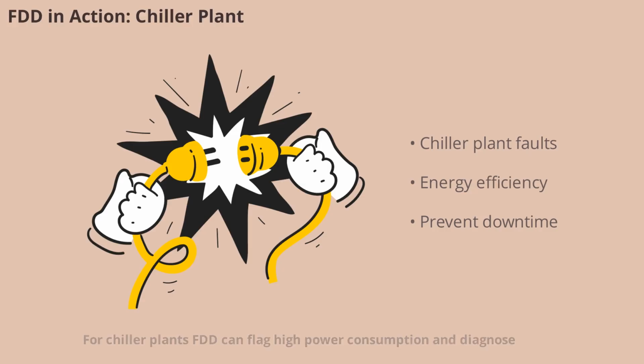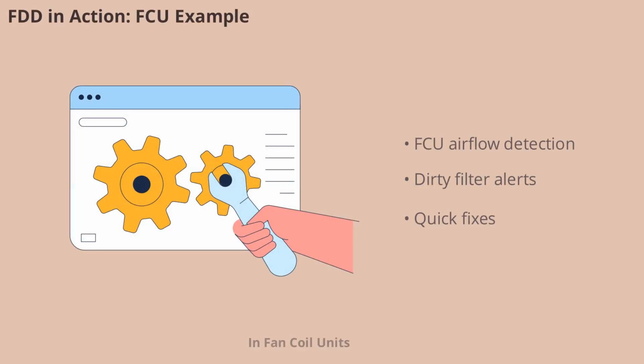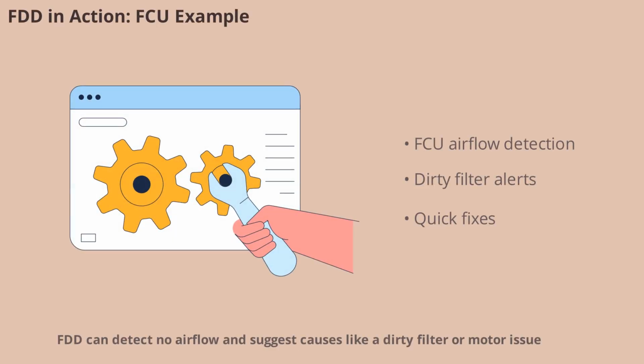For chiller plants, FDD can flag high power consumption and diagnose issues like a failed condenser or poor sequencing. By identifying these problems early, the system helps maintain energy efficiency and prevents costly downtime. In fan coil units, FDD can detect no airflow and suggest causes like a dirty filter or motor issue. This rapid identification allows for quick fixes, ensuring that air quality and comfort are not compromised.